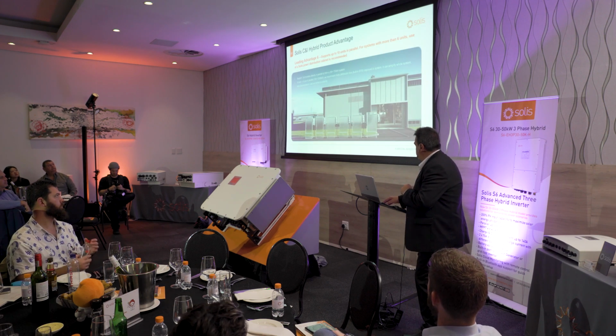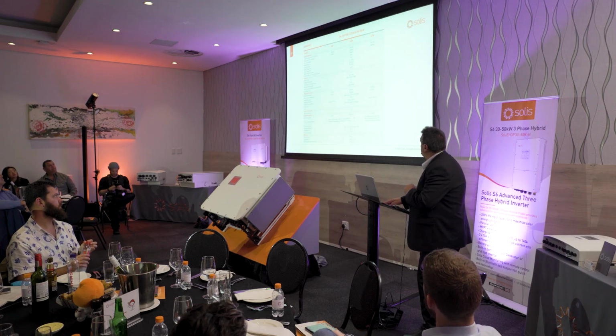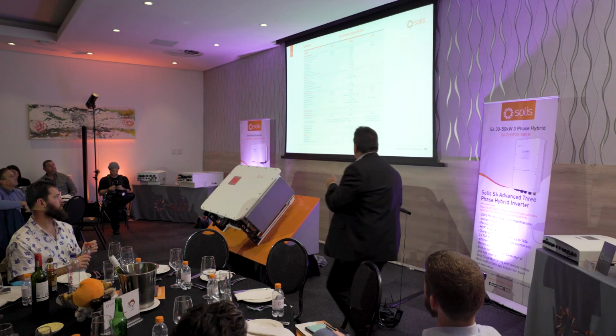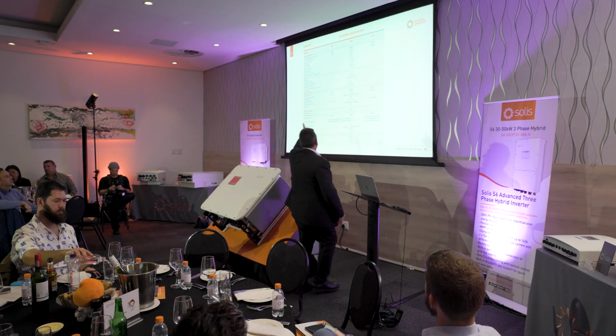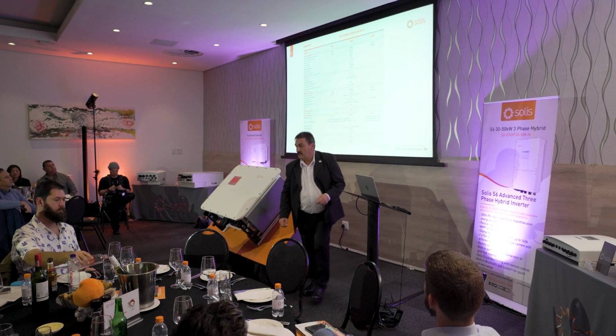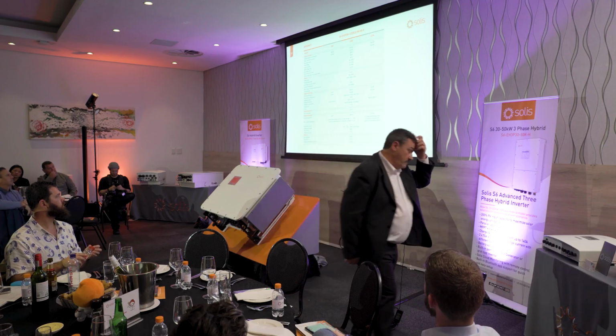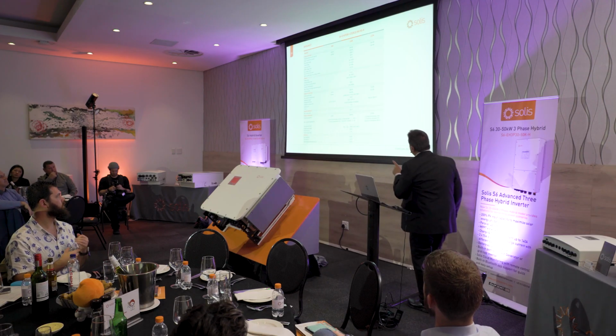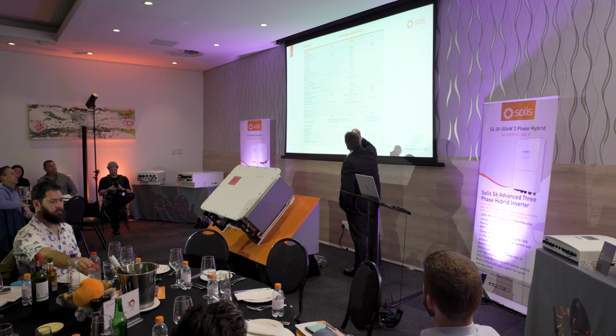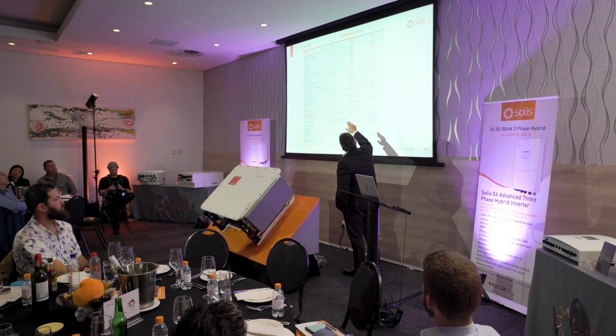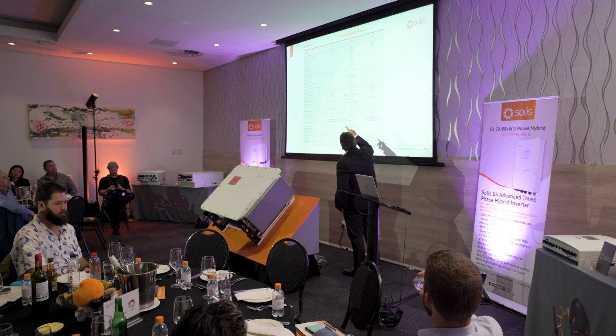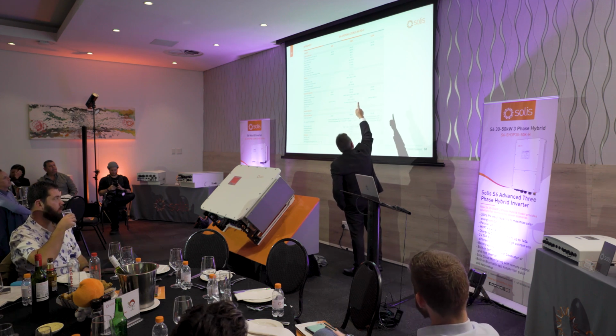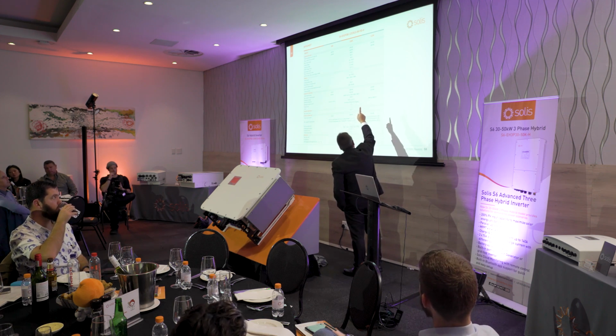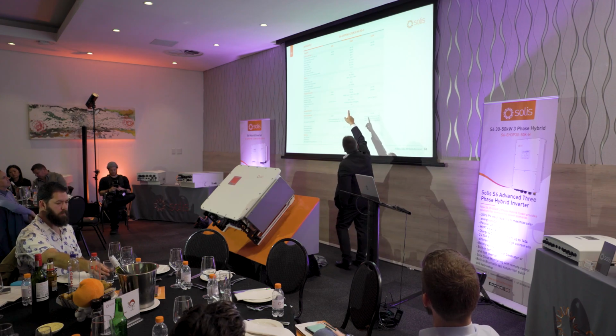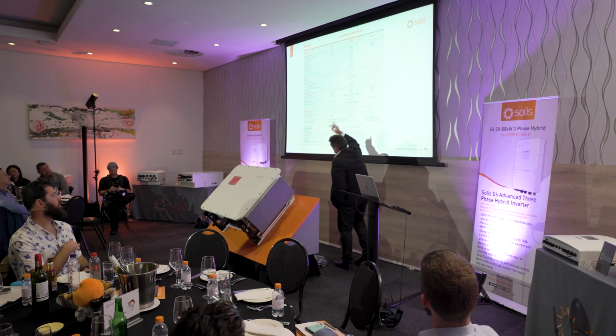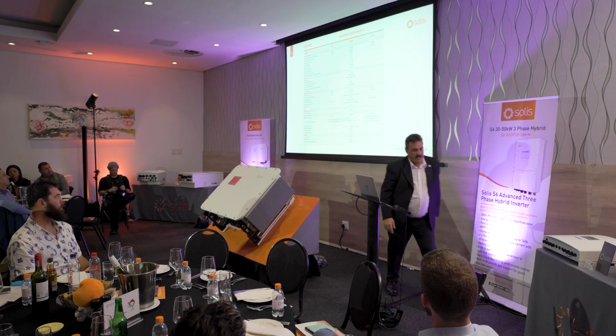We already mentioned 10 units in parallel. Looking at the data sheet, battery voltage goes up to 950 volts DC, from a minimum of 300 volts, and 200 amps total, 100 plus 100. There are 2 charge and discharge ports, CAN or RS485. Capacity at the top is 250 kilowatt, with 10 MPPTs rated at 42 amps each, which comes down to 21 amps per string.